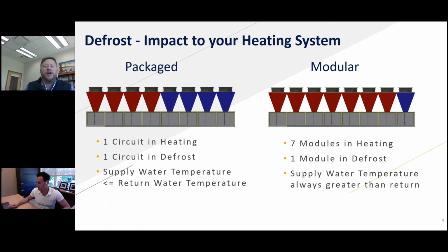So when we look at that, I'm going to talk about the way that we actually go into defrost, depending on what the design of our system looks like. Let's say we have a package system; typically those might have 1 or 2 circuits. If it's a 2-circuit machine, part of the machine is going to go into defrost based on what it's seeing for frosting, and the other part is not. When I show that with the colors, blue is the section in defrost, and the red coils are the section of the unit that's in heating. So in a package unit that shares one heat exchanger, or even if you have 2 separate heat exchangers, part of the unit is pulling heat out of that water loop, which is our heating loop if it's a 2-pipe system, and part of our unit is actually putting heat into it, okay?